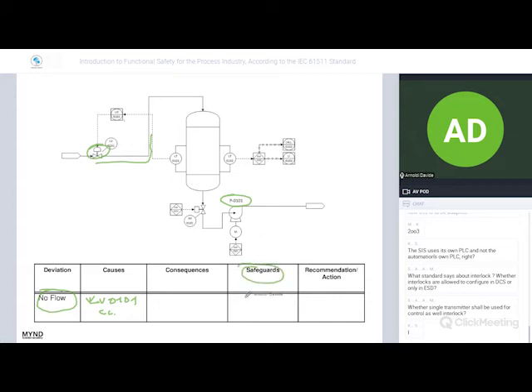Safeguards in the hazard: we have to make a list of all safeguards present. In this case, the safeguards will be the low alarm for the operator console. The other safeguard, already installed, is the safety instrumented function in order to protect the pump. If we have any recommendation, normally we can write it inside the HAZOP according to the decision of the HAZOP team. A recommendation could be, for example, to evaluate installing a new SIF.